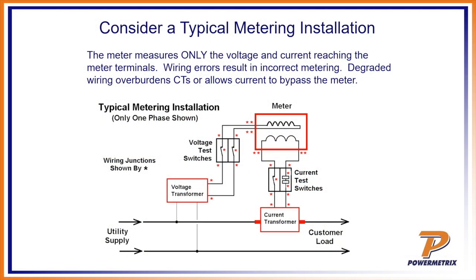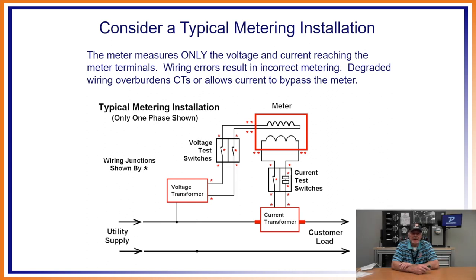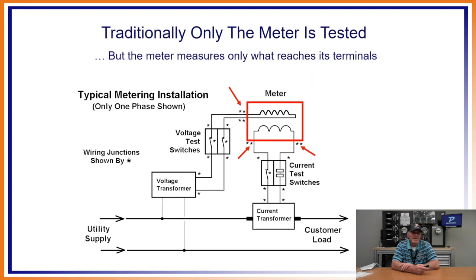Let's look at a typical metering installation. The meter measures only the voltage and current reaching the meter terminals — what's happening besides that, it doesn't know or care. It just knows what's going on right where it's connected. Wiring errors result in incorrect metering. Degraded wiring, overburdened CTs, or current that bypasses the meter — burden is just resistance. Creating resistance through too-small wire or bad connections increases burden, and the two things that hurt CTs are heat and burden. Traditionally, only the meter is tested, but it only measures what's inside that red square. If you just do a phantom load test on that meter, all the rest of that diagram is not included.